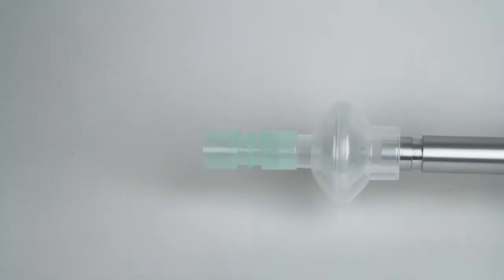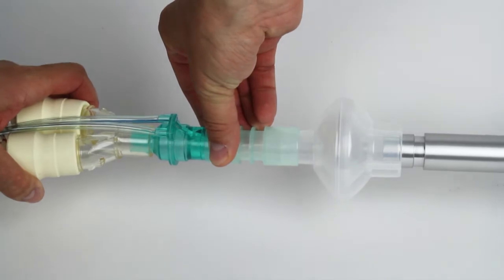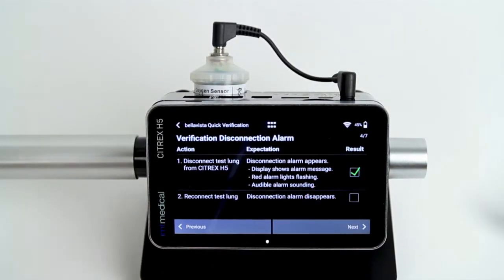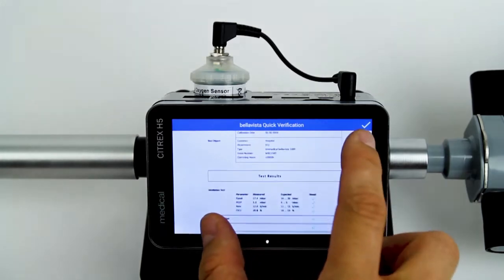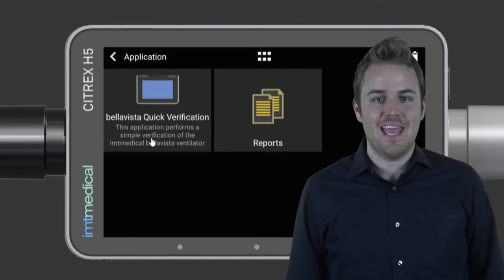The app guides you through the following three simple steps: first, connect the CITREX H5 to a ventilator; secondly, perform verification; and finally, generate a test report. So let's get started. Launch the app bellavista Quick Verification in CITREX H5.